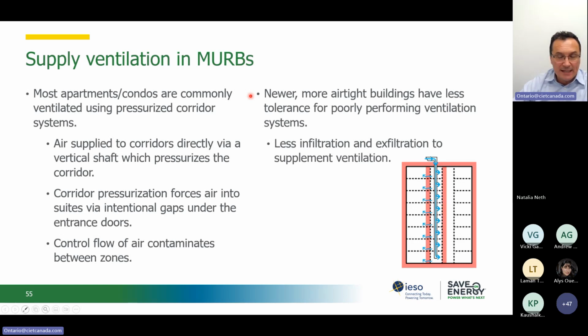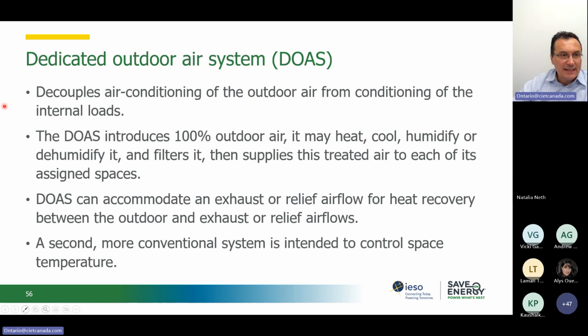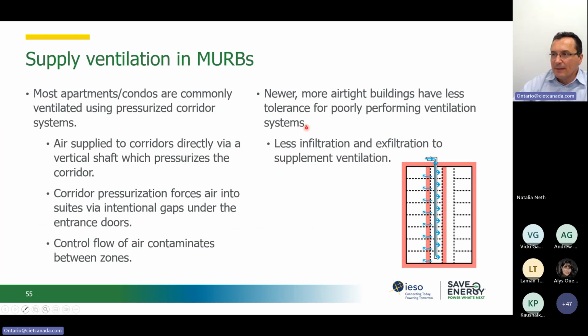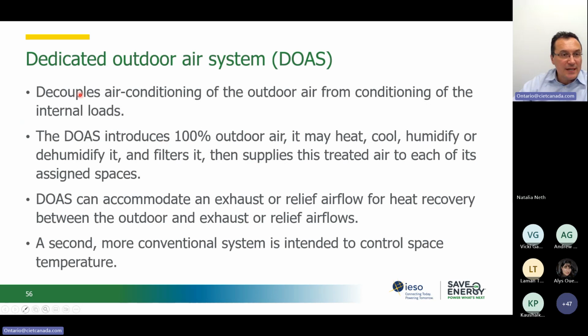So what we are looking at basically is to provide this type of dedicated outside air that decouples, to provide this type of air in each unit separately. So we have dedicated outside air systems in which the only function would be to provide the fresh air in the space. So it's 100% fresh air. We may condition that. We heat it and cool it, or humidify or dehumidify. We filter it so that it meets the requirements for the space, but it's dedicated outside air. So this outside air is meant to compensate for the exhaust air that we remove from the building. Very seldom are we going to use this for space conditioning as a distribution system for the heating and cooling.